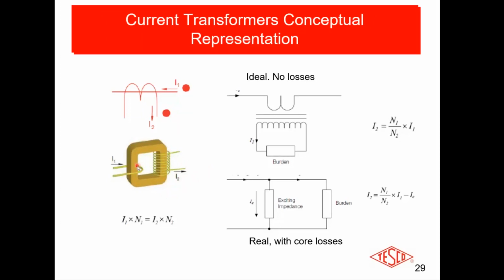However, a transformer requires a certain amount of energy to actually function, all right? And that's called an exciting current. So I have to have just a tiny amount of current go through to get that transformer working. Well, that tiny amount of energy is lost on the primary side, which means that when I come off on my secondaries, I'm always going to be just a little under 100%. So anybody that tells you, oh, I've got a transformer that's registering over 100%, there's something wrong, okay?